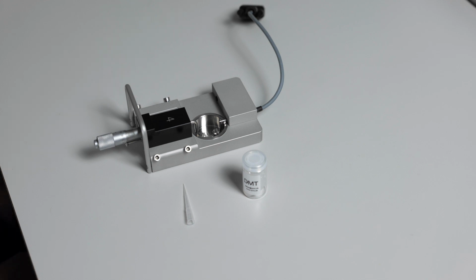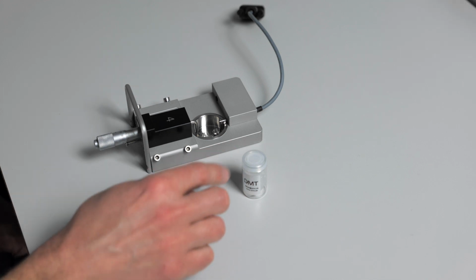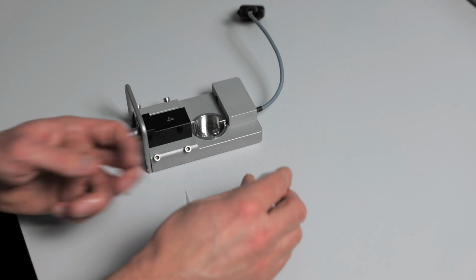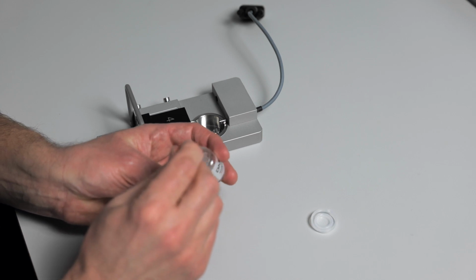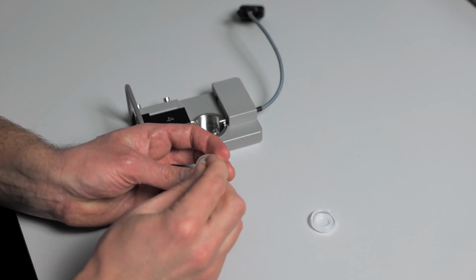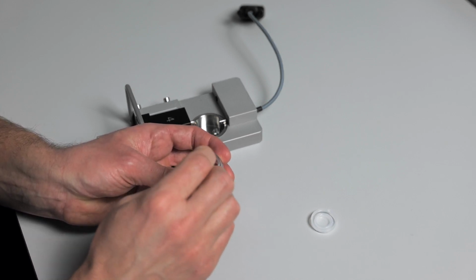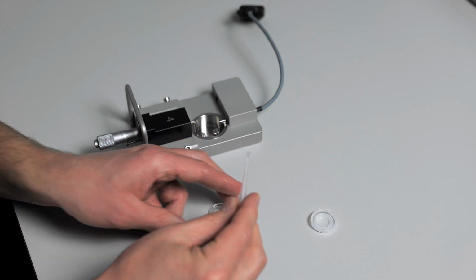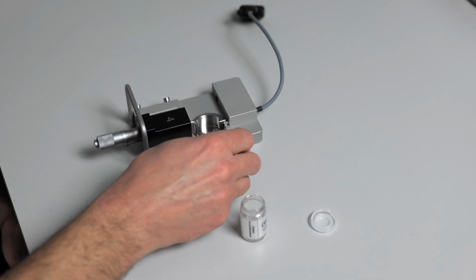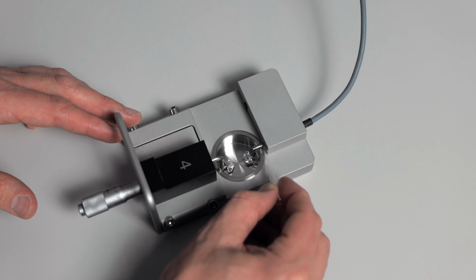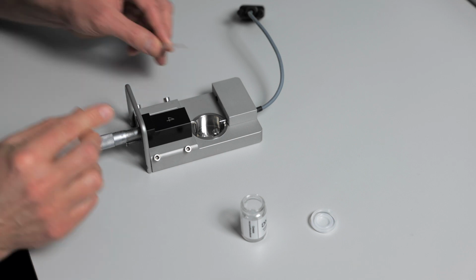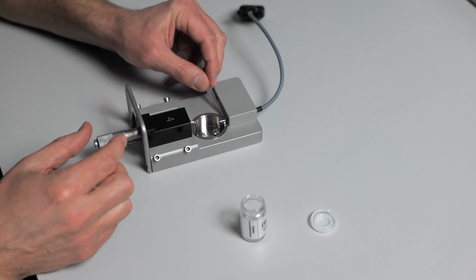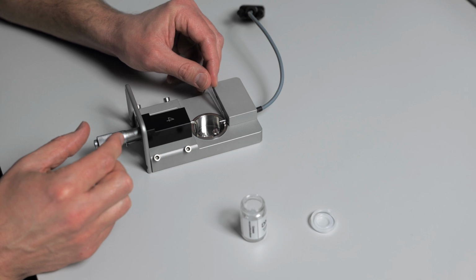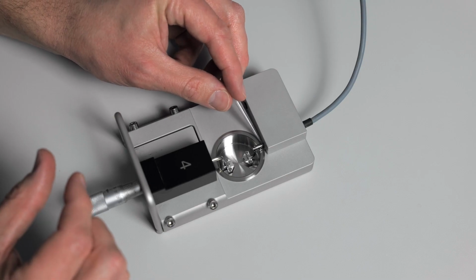For the first method of re-greasing, all you need is the pipette tip and the clear silicone grease that came with your system. So remove the lid from the grease container. Dip the pipette tip in there to get some grease on the tip. And then you will carefully and gently apply this around the transducer pin. Any excess you get in the surrounding area is okay, and it's easy to wipe off.